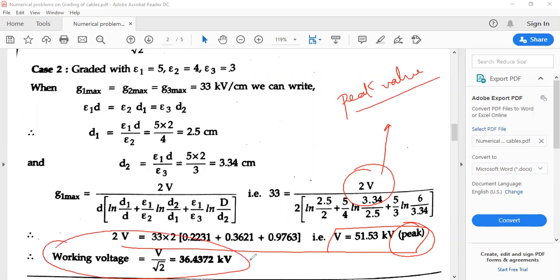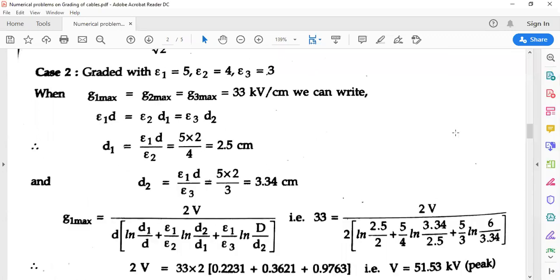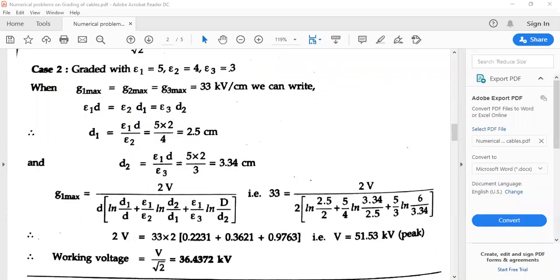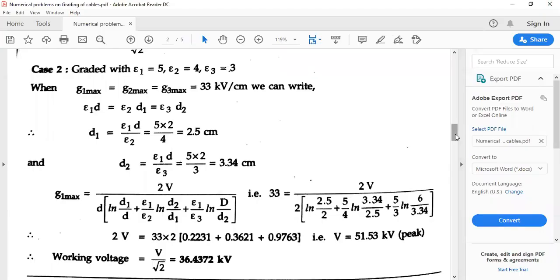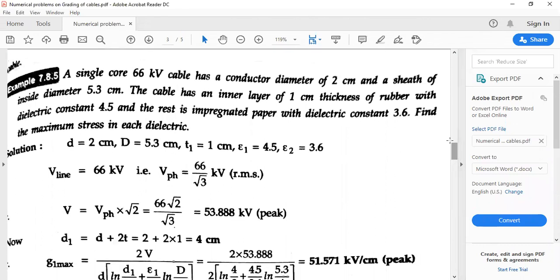If you have this peak value and you need to get the working voltage, the working voltage on the cable is 36.4372 kV. That's how you find the working voltage on the cable. Next, you can go to a similar type of problem where the working voltage is given and you need to find the diameters of the individual cables.